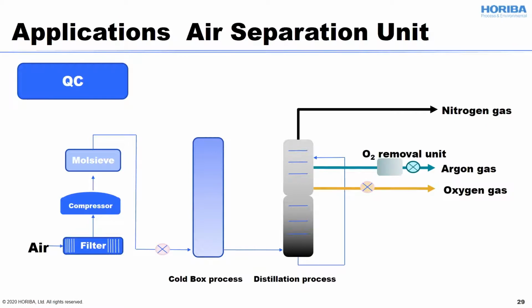Air separation unit. There are many gas providers in the world. An air separation unit might be in the plant to feed plant utilities such as nitrogen, argon, oxygen. Let me explain the cryogenic air separation process a little bit here. Air goes through the filter, which captures the oil and dust in the ambient air. Air is then compressed and goes through a molecular sieve process to remove H2O and CO2. Because if the feed contains H2O and CO2, then a formation of ice or dry ice may occur in the cooling process. The cold box chills the air at minus 173 degrees C. So before entering the cold box, you want to remove H2O and CO2 completely.